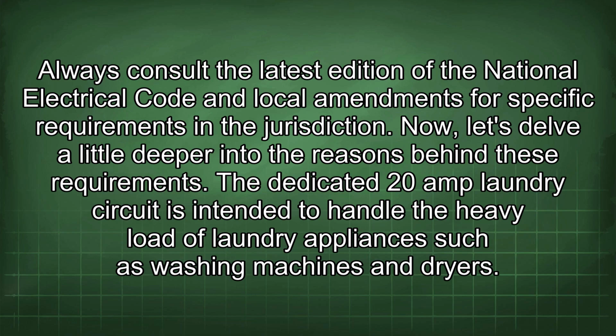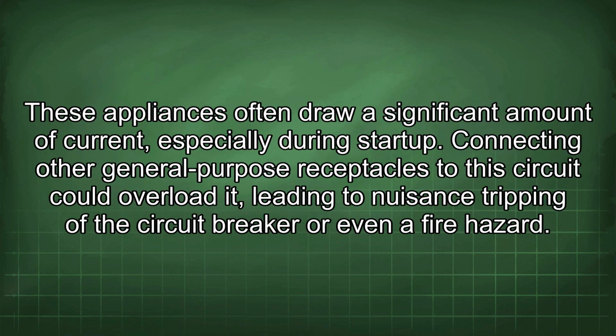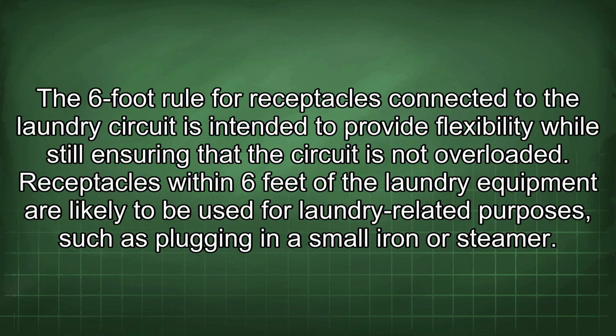The dedicated 20-amp laundry circuit is intended to handle the heavy load of laundry appliances such as washing machines and dryers. These appliances often draw a significant amount of current, especially during startup. Connecting other general-purpose receptacles to this circuit could overload it, leading to nuisance tripping of the circuit breaker or even a fire hazard. The 6-foot rule for receptacles connected to the laundry circuit is intended to provide flexibility while still ensuring that the circuit is not overloaded.